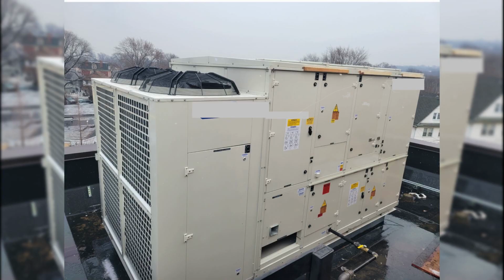If a project is not bound to comply with the Green Schools Guide, sound pressure levels of 45 dBA, NC 40 are acceptable. 17. Carbon reduction. If existing boilers have less than 15 years of life, they should be replaced with heat pump systems. 18. For buildings with pitched roofs, indoor mechanical equipment rooms, MERs, are more optimal for central units.